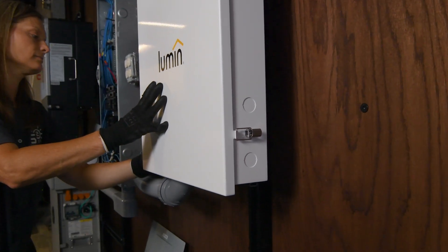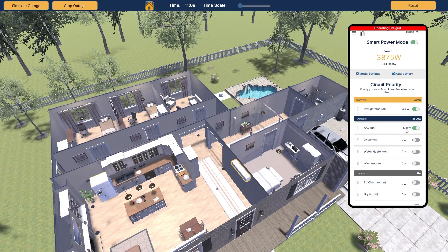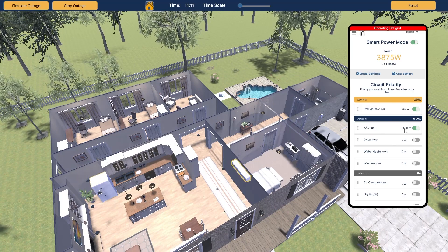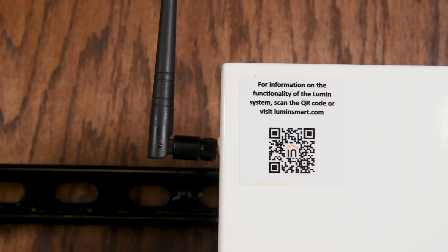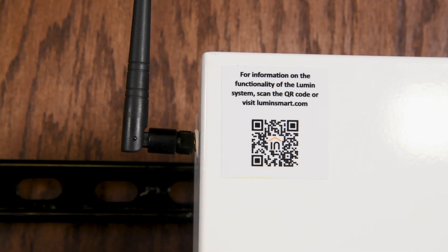You can mount the Lumin Smart Panel in various ways, connecting it to your existing panel through different knockouts, making it incredibly versatile. The primary function of the Lumin Smart Panel is intelligent load management. During an outage, it automatically reduces the total load to prevent overwhelming your backup storage system. Compatible with both generators and battery backups, the panel is designed to work seamlessly with any setup. By shedding unnecessary load circuits during an outage, Lumin maintains the overall demand on your energy storage system within specified limits.